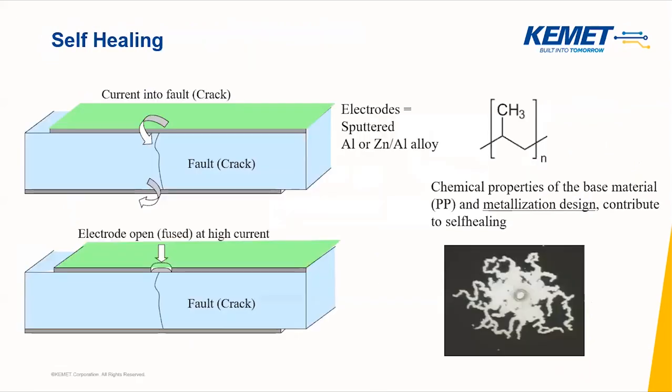Another important characteristic of film safety capacitors is their self-healing capability. What is self-healing? The self-healing property of metallized film dielectrics is basically their ability to self-regenerate an internal drop of insulation resistance. This ensures a safe failure mode in AC filtering applications where electrical noise and peak voltages are added repeatedly or occasionally to the fundamental frequency.